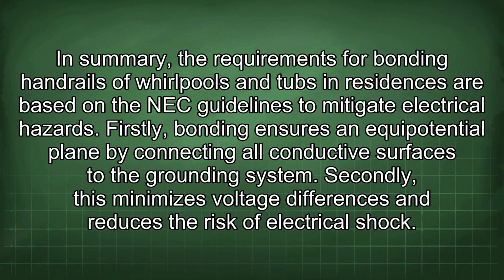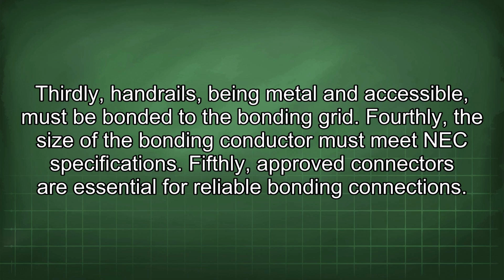In summary, the requirements for bonding handrails of whirlpools and tubs in residences are based on the NEC guidelines to mitigate electrical hazards. Firstly, bonding ensures an equipotential plane by connecting all conductive surfaces to the grounding system. Secondly, this minimizes voltage differences and reduces the risk of electrical shock. Thirdly, handrails, being metal and accessible, must be bonded to the bonding grid. Fourthly, the size of the bonding conductor must meet NEC specifications. Fifthly, approved connectors are essential for reliable bonding connections.